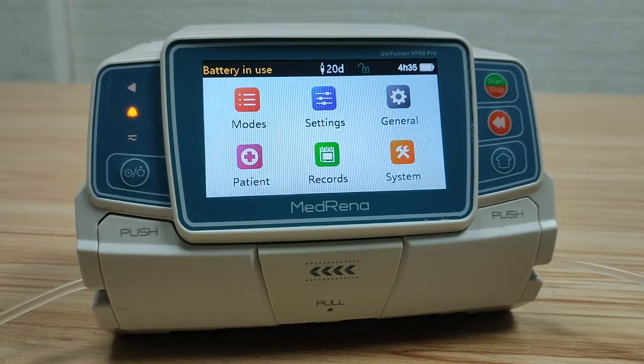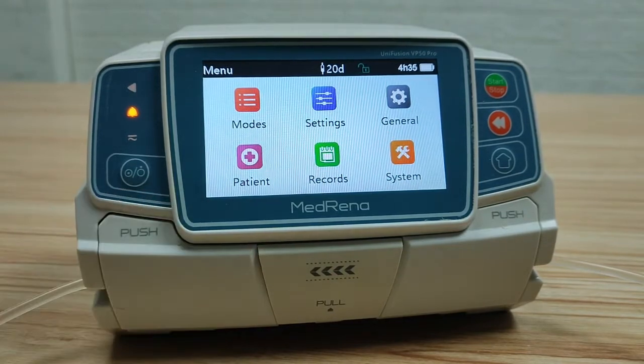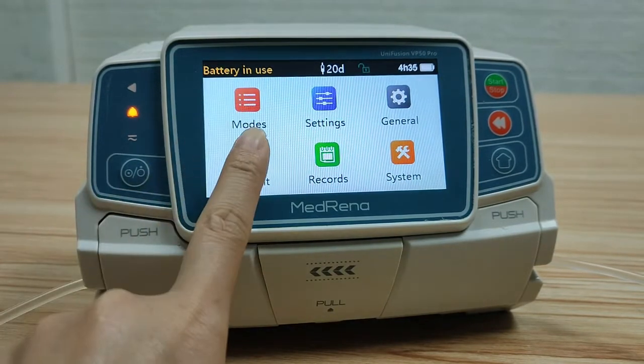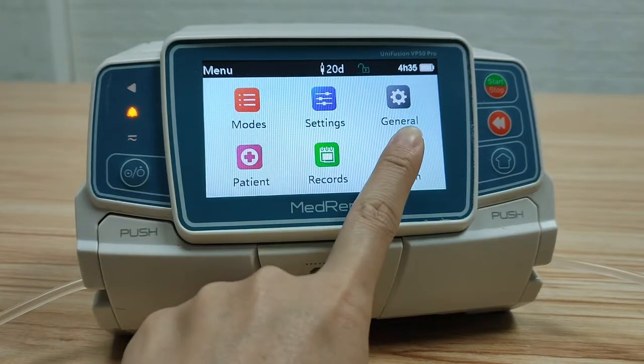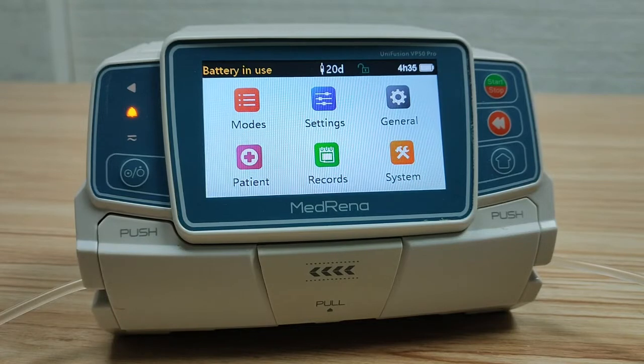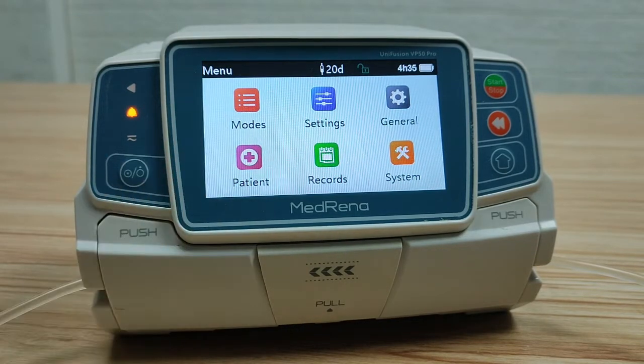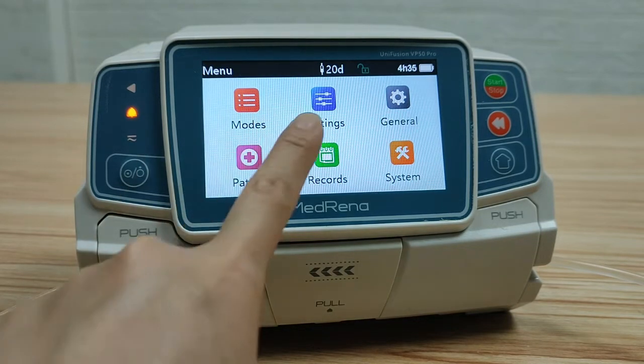This video introduces the settings of the MedRena infusion pump, model name Unifusion VP50 Pro. This is the home page. There are six boxes on the screen: modes, settings, general, patient, records, and system. In the last video we introduced modes; next let's look at the other boxes one by one, starting with settings.